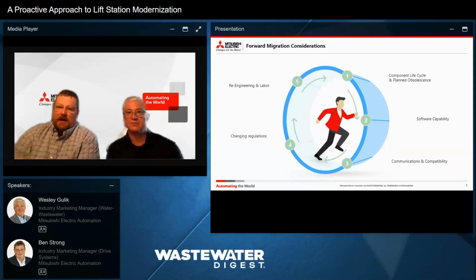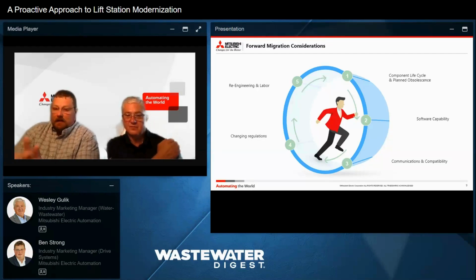In municipalities, we have to have a long-term plan, and this is how long these lift stations typically are designed for. Most municipalities are planning out 5 to 10 years with what they're going to upgrade. Well, is the software you're using today going to be compatible with the software that vendor offers 5 years from now? Questions to ask. Communications, especially if you're on a serial-based communication platform now, going to the future, do I need to be on Ethernet, or my vendor and my control scheme, is it going to grow? So you have to choose the right formats and how you communicate.